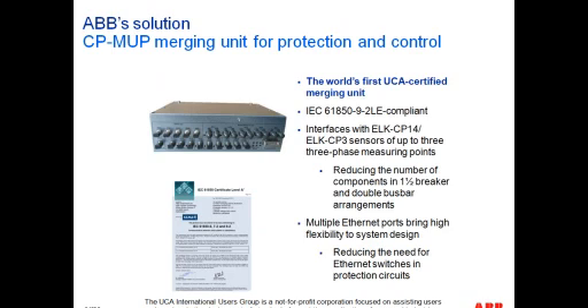And a little bit of information about our main merging unit. This was the world's first UCA certified merging unit, which interfaces with the CP14 and CP3 sensors, and each merging unit has the capability of up to 3 three-phase measuring points. So that's a total of 9 analog quantities, and this obviously provides significant reduction of components for breaker and a half schemes, for example.